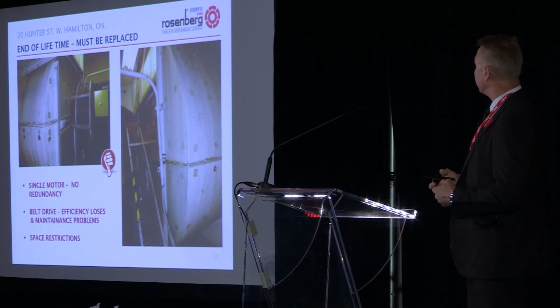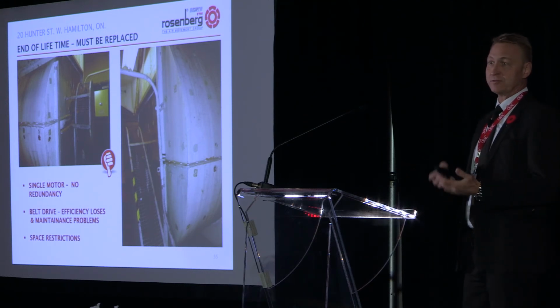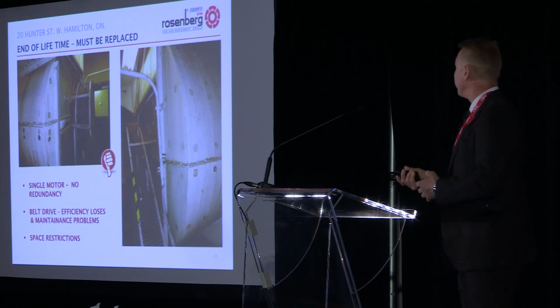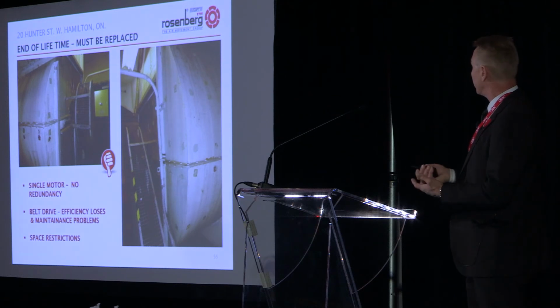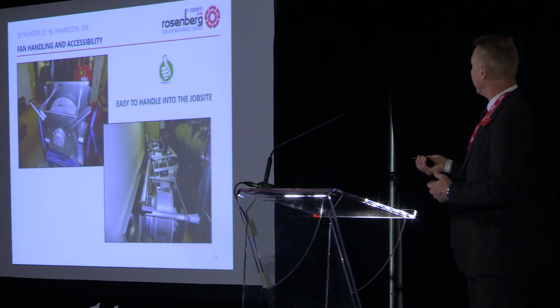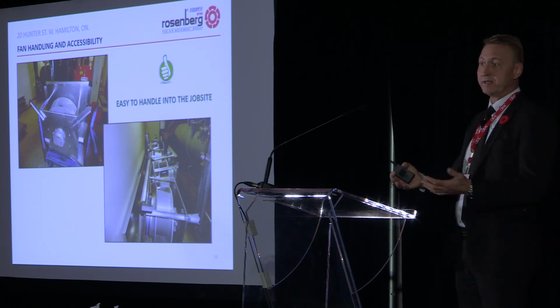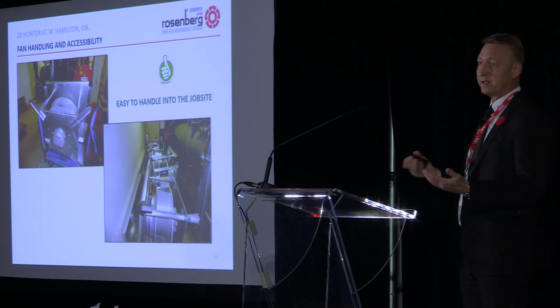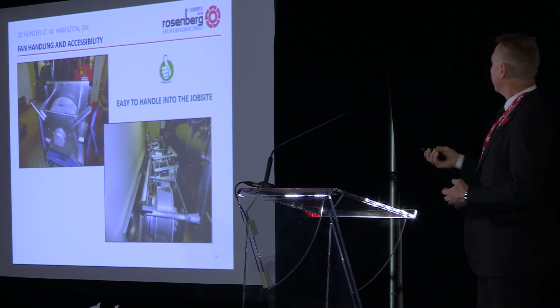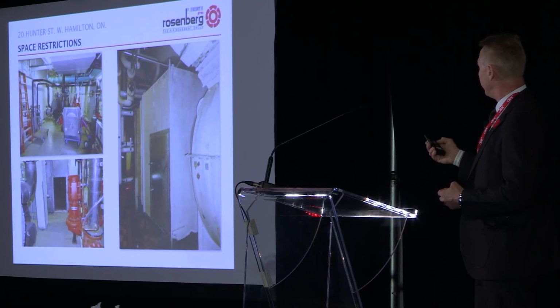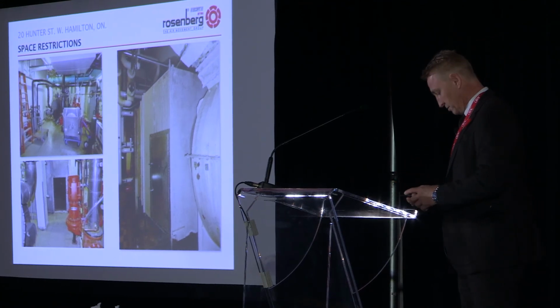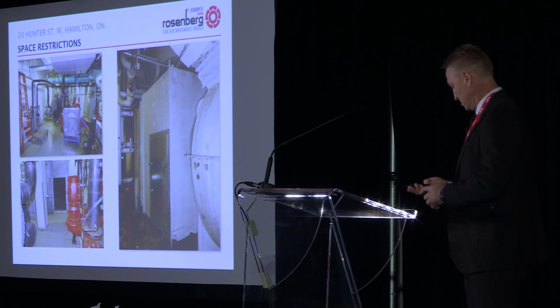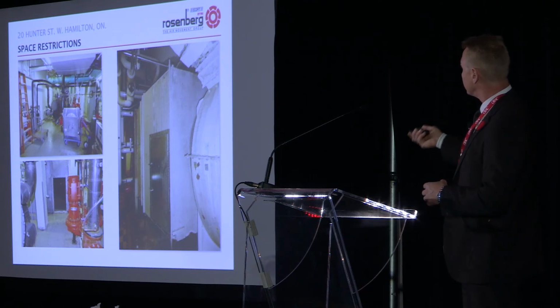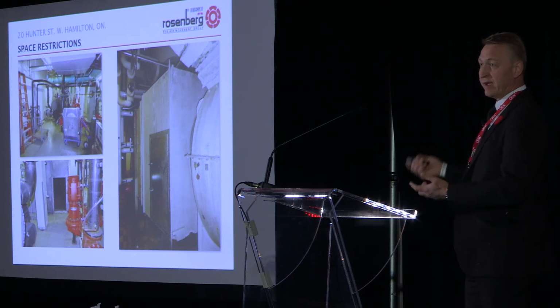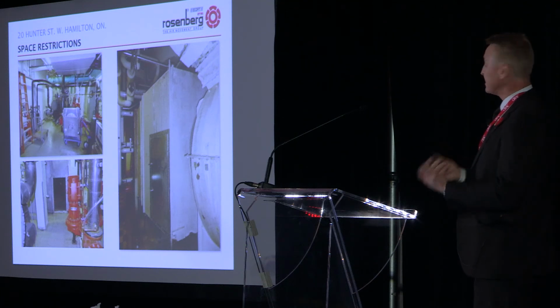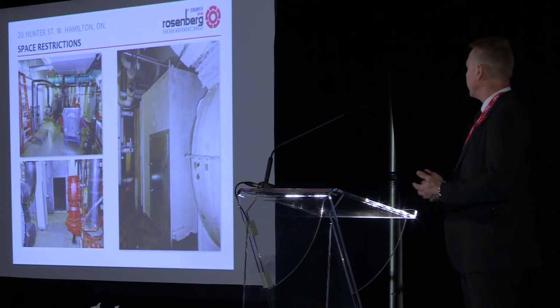So in Hamilton, the fan was still operational, but it was running out of time, like at the end of the life, and that's when we started to work on this project. Because of the compactness and lightweight, our fans were quite easy to handle and bring them inside the building, inside the technical room, with all this equipment. The fan grid was installed in this box, while the old fan was still in place and running. And it was disconnected and demolished after our fan grid was commissioned and fully operational.